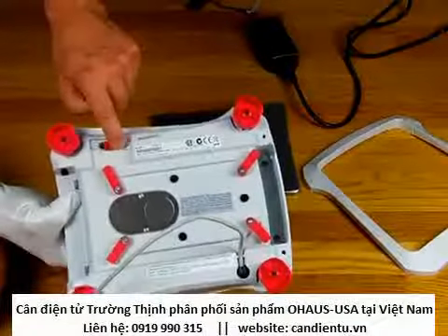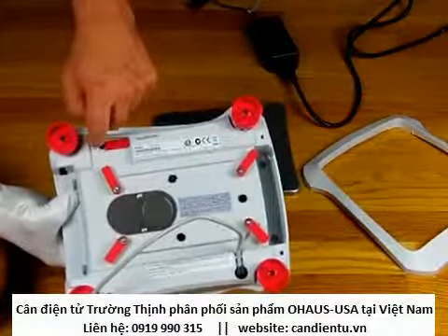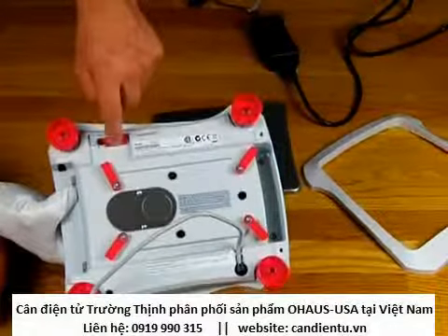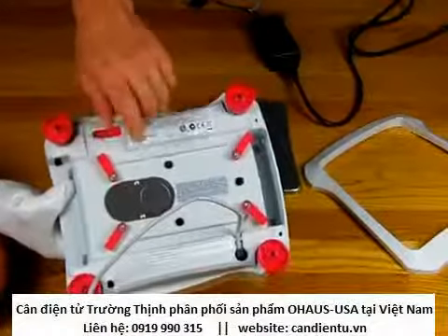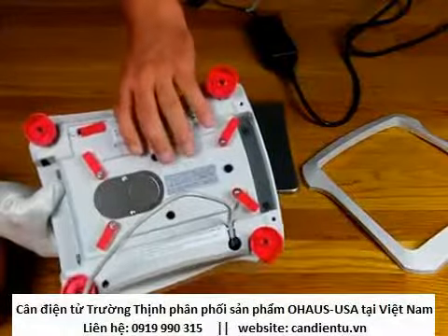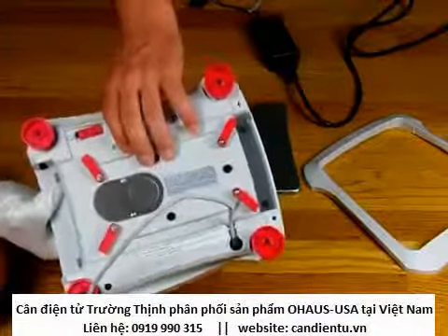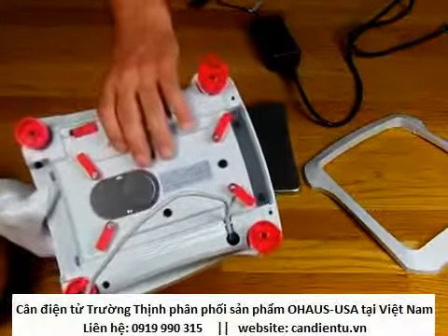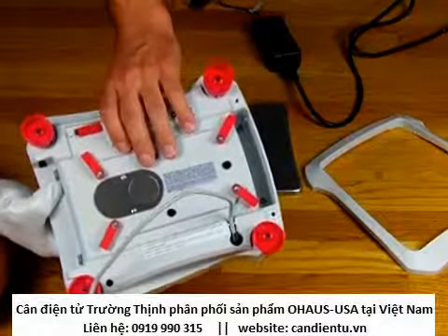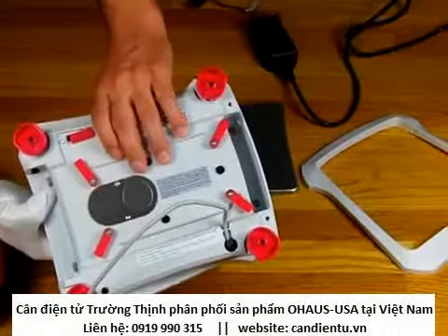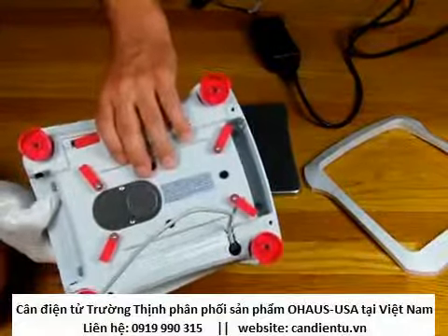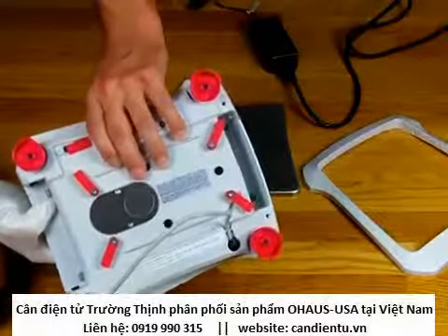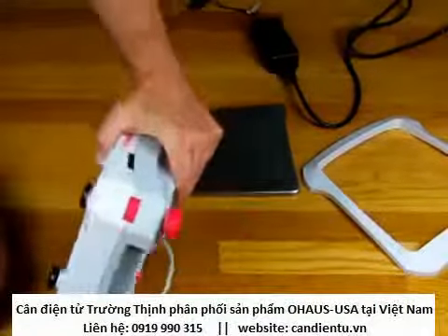When the balance is put into legal for trade mode, someone from Weights and Measures would put a cable through the bottom of the balance and crimp this. The Ohaus Explorer series are all pending legal for trade approval, which should come through at any time. So this balance could be used for jewelry applications, weighing gold, silver, or anything sold by weight - the Ohaus Explorer would be a great balance.